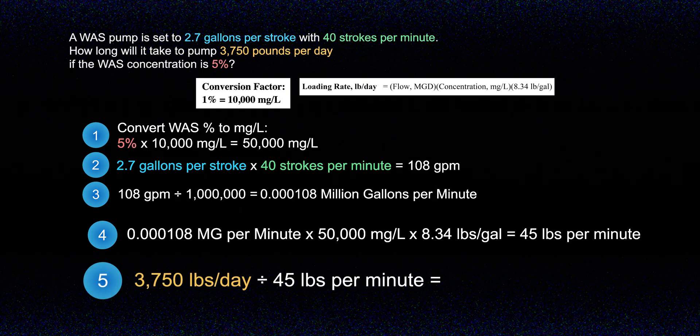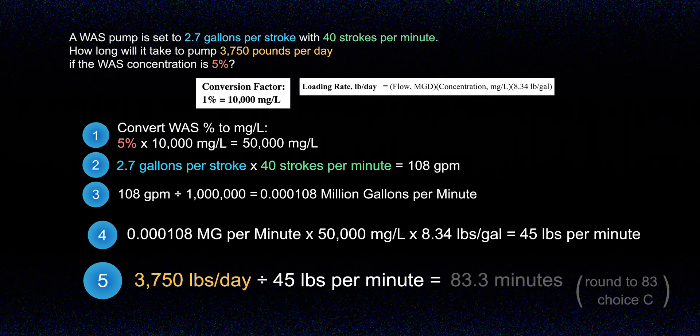In step 5 we bring it all together. Now that we know the amount of solids being pumped per minute, we can figure out how long it will take to pump 3,750 pounds of solids contained in the waste-activated sludge. We simply take the 3,750 pounds per day and divide by the rate of 45 pounds per minute, giving us 83.3 minutes, which rounds down to 83 — choice C.